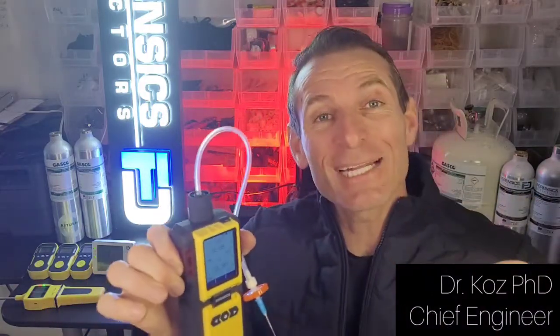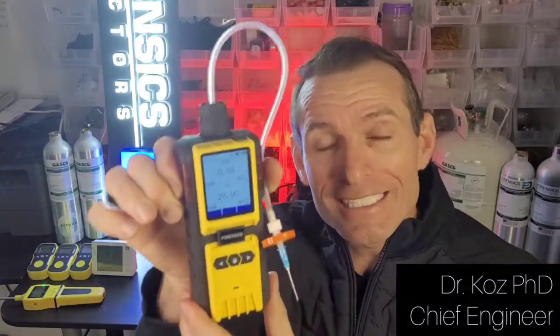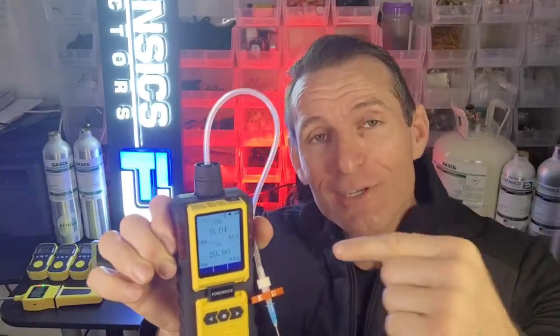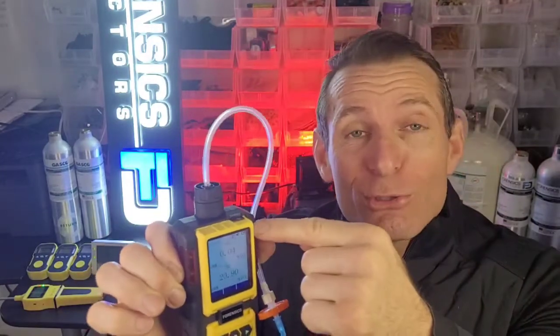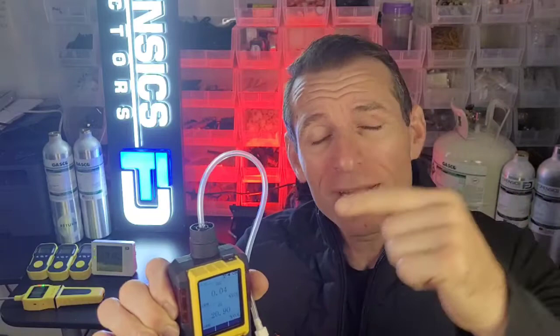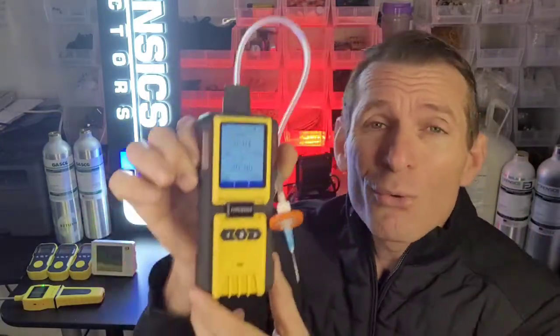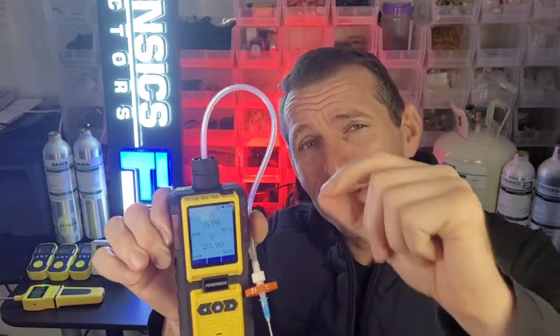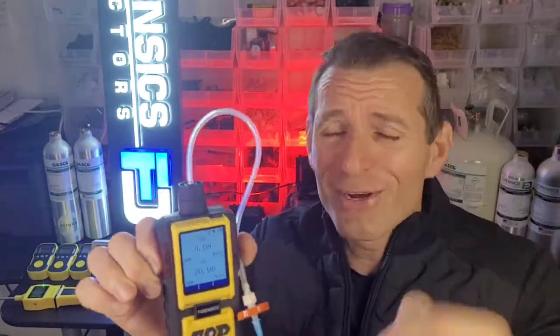Welcome to Forensics Detectors. I am Dr. Koz, your gas meter, gas detector, and today I am your headspace analyzer expert. We are presenting our 600 model CO2 and oxygen analyzer — CO2 carbon dioxide from 0 to 100% full range and oxygen 0 to 30%, both with 0.01% resolution. Very fine measurements to make sure you get your numbers bang right on.